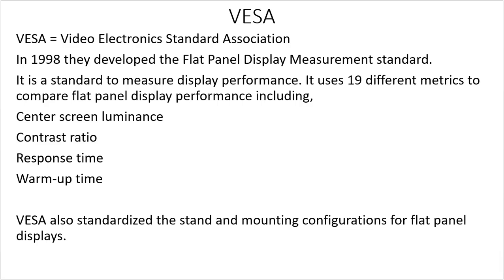VESA — the Video Electronics Standards Association — in 1998 developed the flat panel display measurement standard to measure display performance. It uses 19 different metrics to compare flat panel display performance. The ones that matter to us are: center screen luminance, contrast ratio, response time, and warm-up time. The VESA standard is what we use to test the monitors at the modalities — for example, the monitor technologists use to review CTs or MRIs. We generally calibrate those monitors to VESA standards.